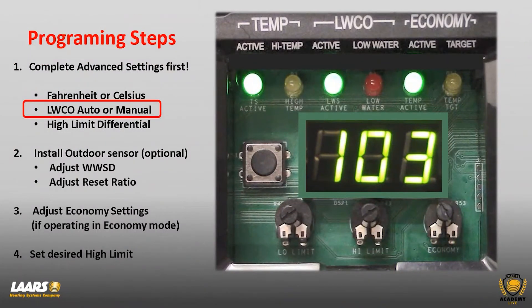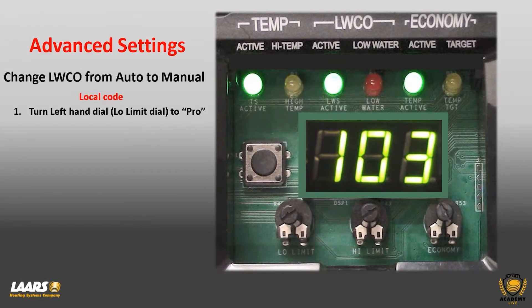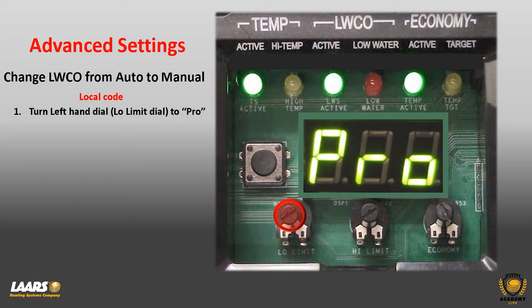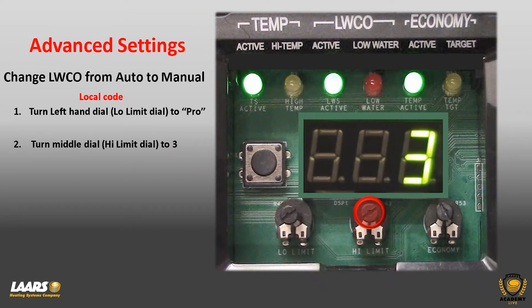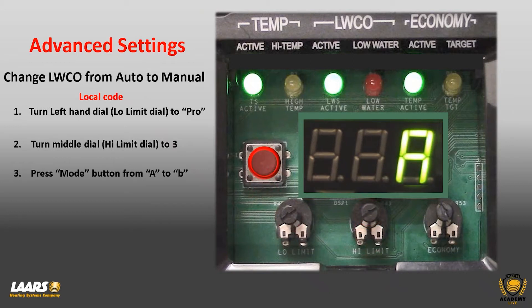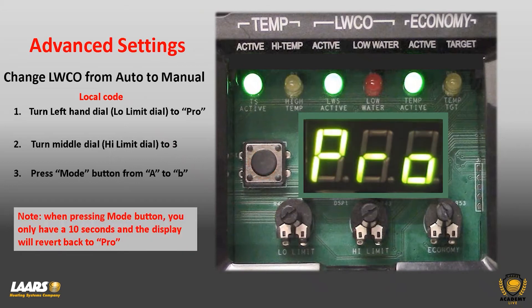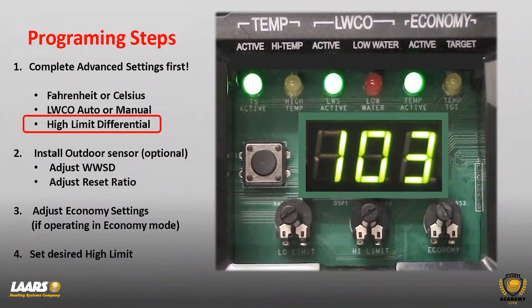To change your low water cutoff from auto reset to manual reset, start with the left-hand dial and make sure you're in PRO for programming. Choose the middle dial and turn it to the number three. Press the mode button once and the letter A will appear for auto; press it a second time and the letter B will appear for manual reset. It will revert back to programming after 10 seconds.